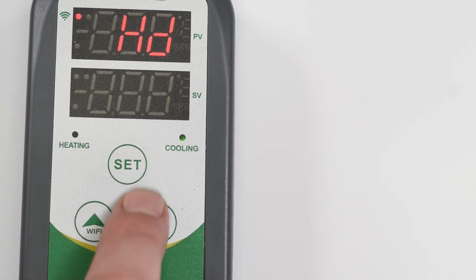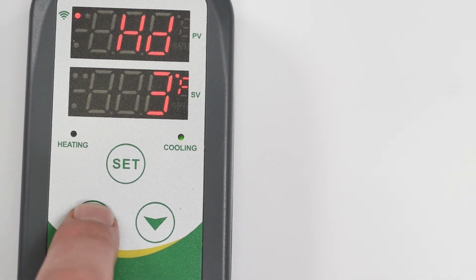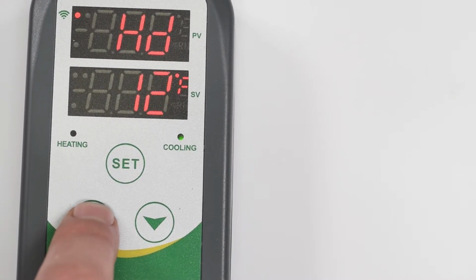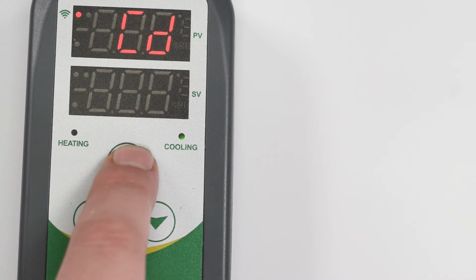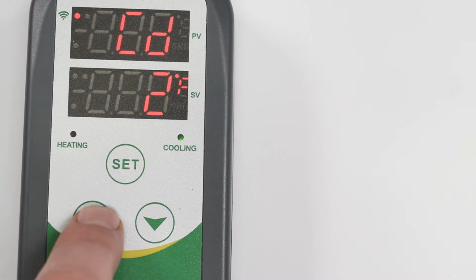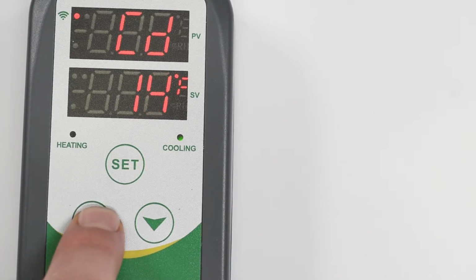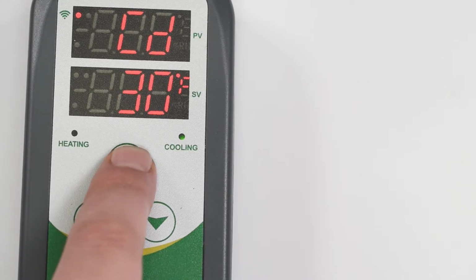Press set again to go to HD, which stands for a heating difference value. This is the number of degrees below the target temperature that you want the chamber to get before turning on the heater, with a maximum of 30 degrees. And then up next is CD, or cooling difference, which is the same thing except for how much hotter than the target value it will get before turning on the cooling device.